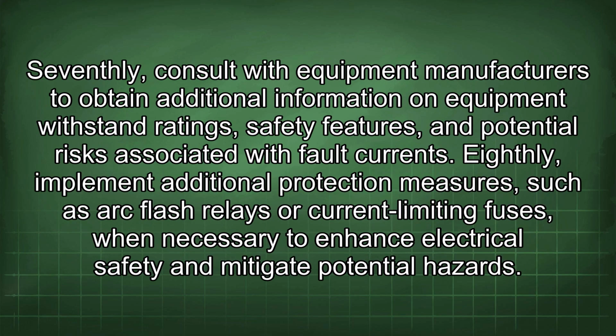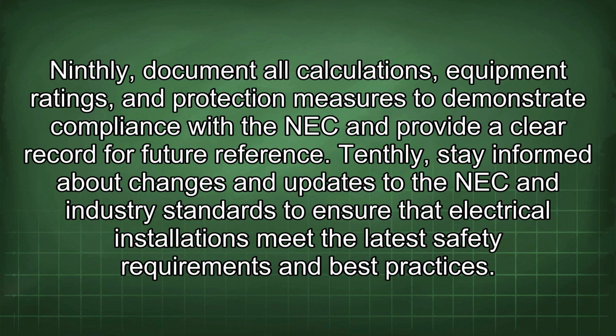Seventhly, consult with equipment manufacturers to obtain additional information on equipment withstand ratings, safety features, and potential risks associated with fault currents. Eighthly, implement additional protection measures, such as arc flash relays or current limiting fuses, when necessary to enhance electrical safety and mitigate potential hazards. Ninthly, document all calculations, equipment ratings, and protection measures to demonstrate compliance with the NEC and provide a clear record for future reference. Tenthly, stay informed about changes and updates to the NEC and industry standards to ensure that electrical installations meet the latest safety requirements and best practices.